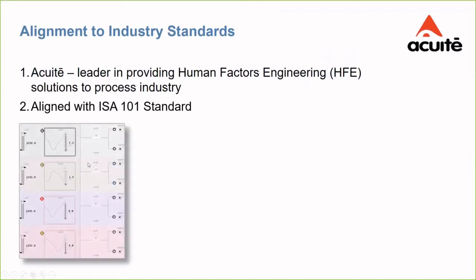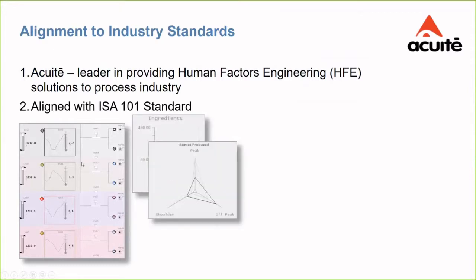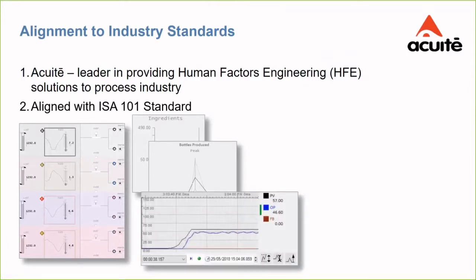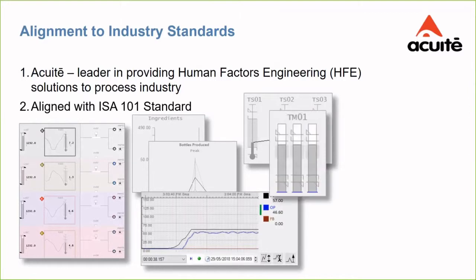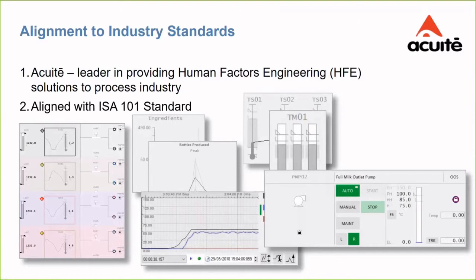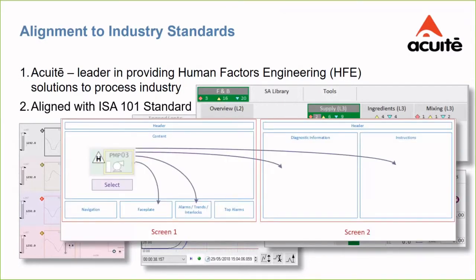Here are a few examples of symbols that have been added to the library, designed to provide all the information relevant to an operator in context, and applicable as templates to your projects. In addition, multi-monitor support allows the operator to have, for example, a pump on the left-hand monitor, and upon selecting that pump not only do the face plate and alarms appear, but additional diagnostic information and instructions can appear on the second monitor.